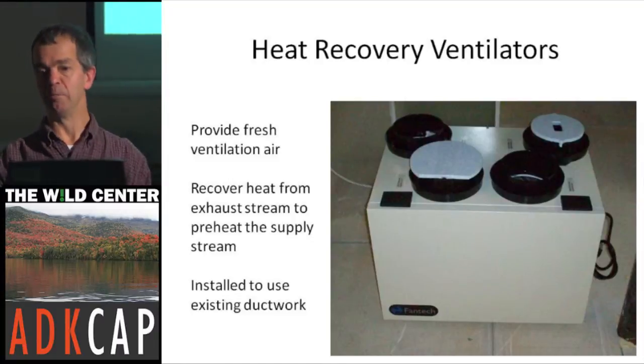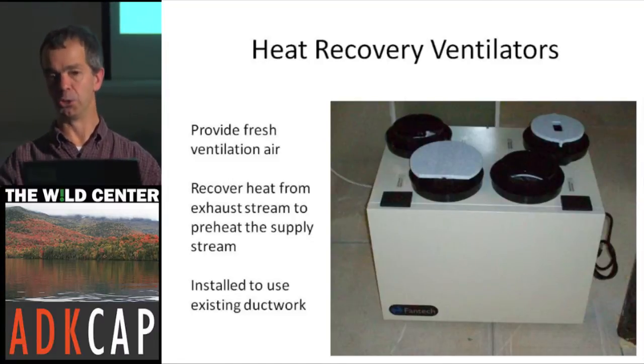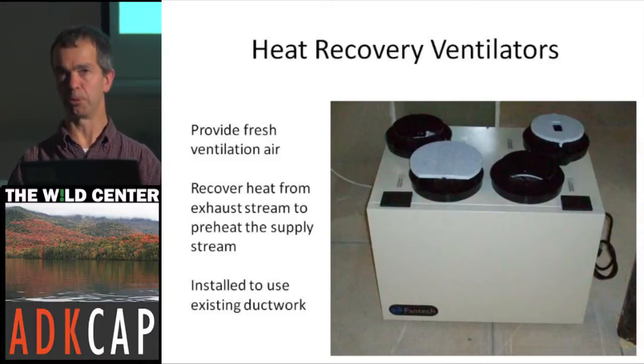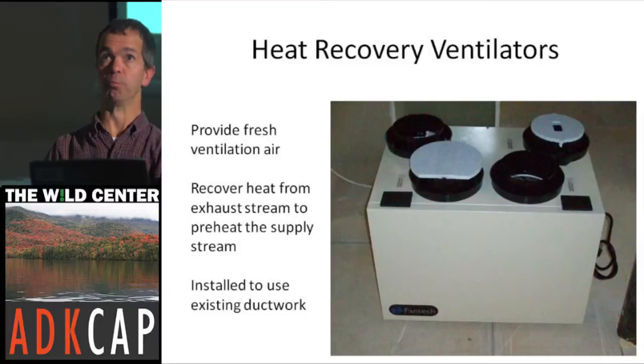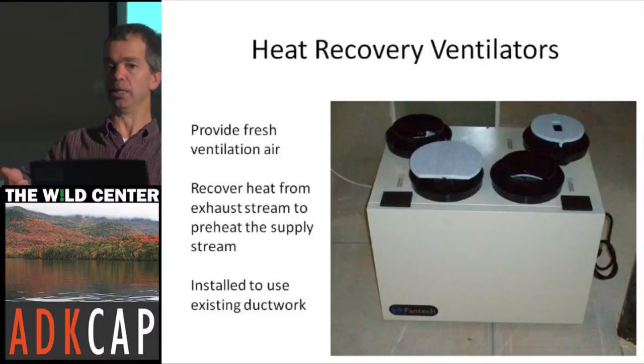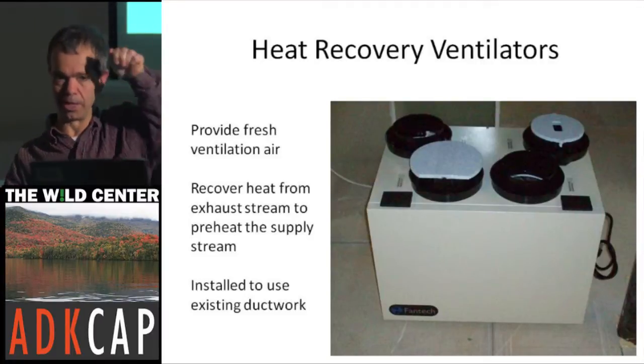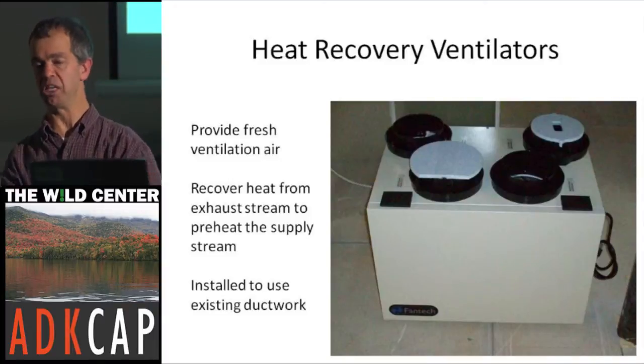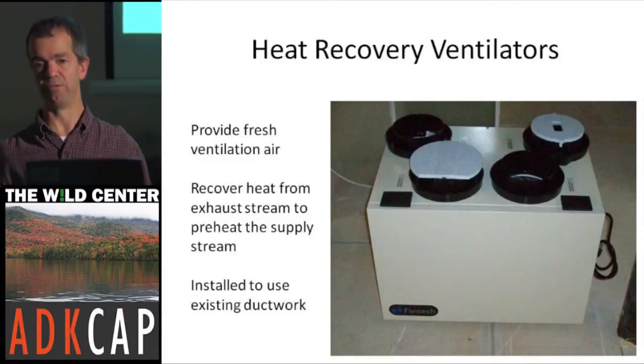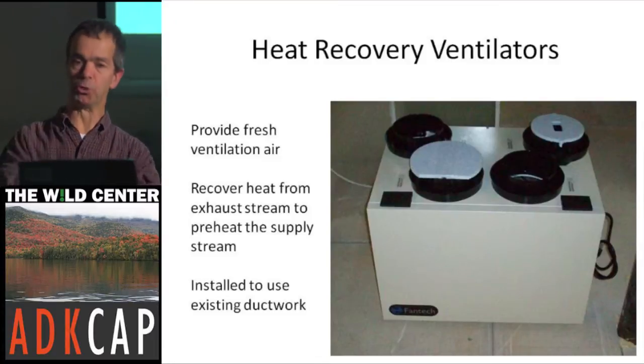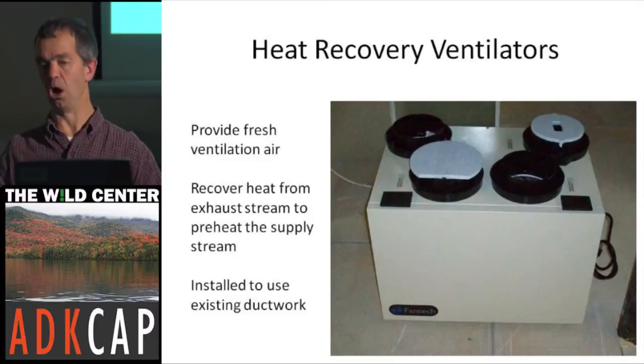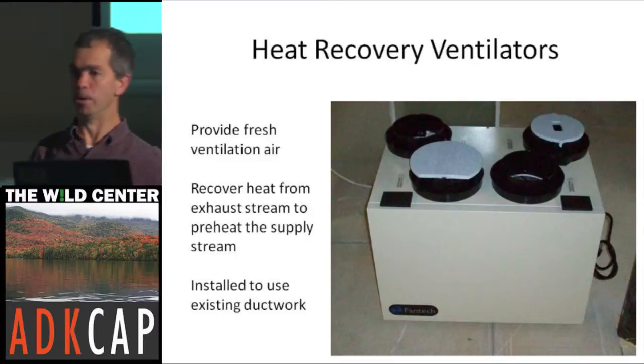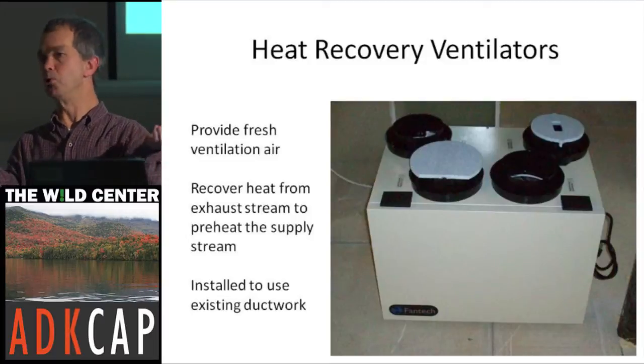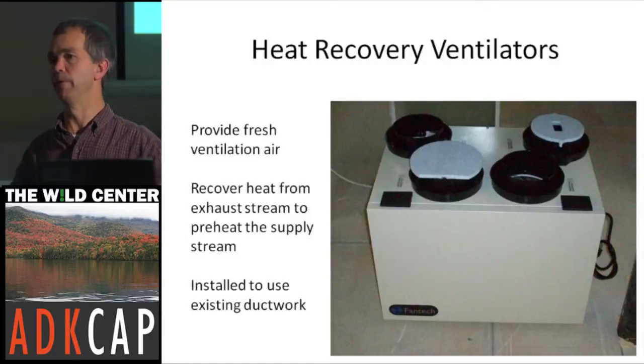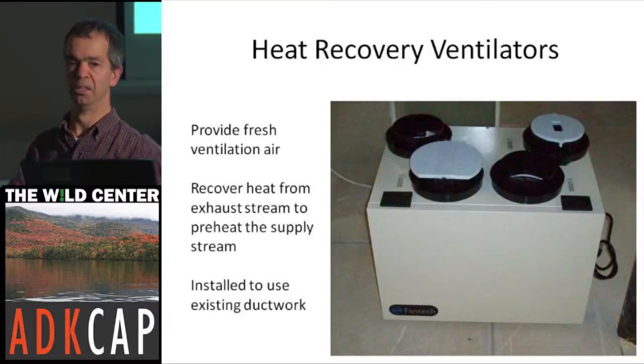Typical HRV, basically there's an inlet port, an exhaust port, and then discharge ports to the fresh air. Typically you put fresh air returns to the bedrooms, and you bring returns from areas where you're cooking, bathrooms. Like in our house we have a timer. If I go to take a shower, I turn the timer, it throws the fan into higher speed, it pulls the moisture out of the bathroom and then reduces back down to the low speed, which is always circulating the air. Continuous exchange? Yeah, it runs all the time. Where we live, because we're in the Adirondacks, we use our windows in the summer. But some people, they're in a city, they don't want to do that. You can run it continuously.